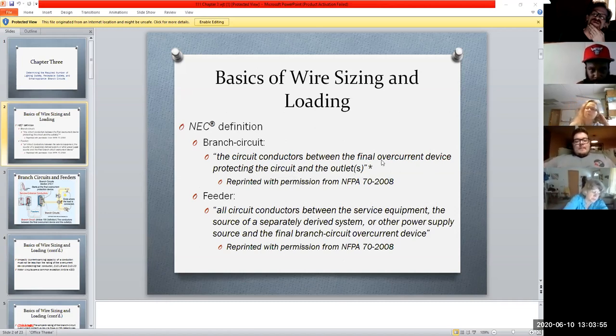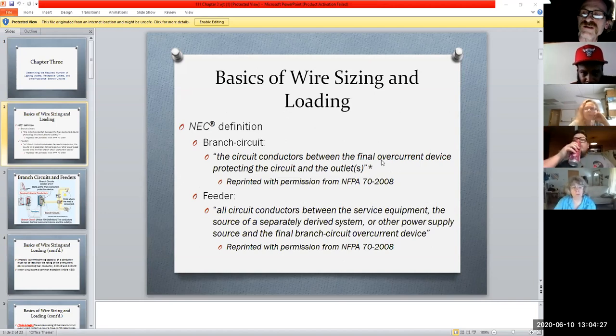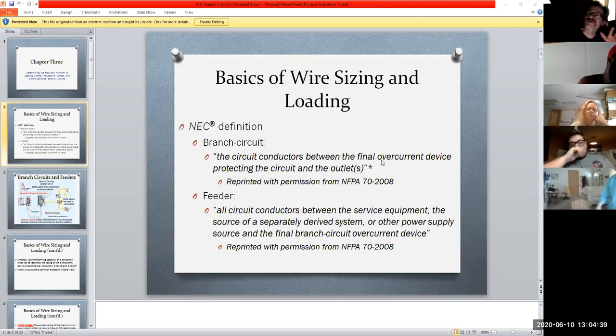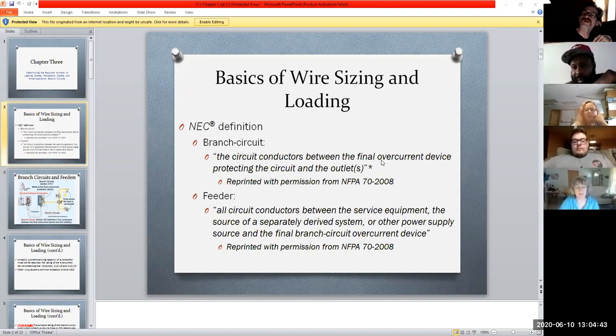And what do they mean by an overcurrent device? Well, that's anything that's going to trip in the event that you have too much current going into a line. Let's say I have a rated line of 20 amps, and all of a sudden it starts pulling more than that, like 25 amps. It has some kind of hard short to it. Well, you want the fuse to blow, the circuit breaker to trip, or something, to de-energize that to prevent more damage occurring. So your final overcurrent device in this case is usually back in the service panel, and that's your circuit breaker. That's your weakest link, if you will, because now I've set my circuit up to be based on that overcurrent device. So if I have a 15 amp breaker in there, then my limit is 15 amps. I have a 20 amp breaker and so on.